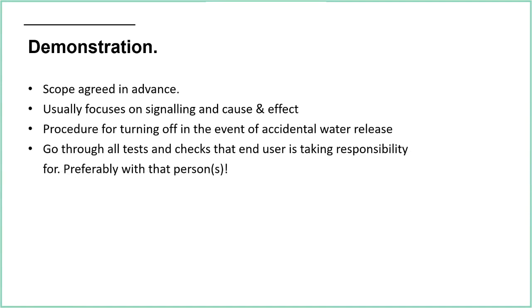Or it might be a case of 50%. So it might be a case of, just show me half of all the monitored valves, and I'll take it on faith that the other 50% work. Or it might be another percentage that is chosen. So say you're picking things at random to show that things are working without going through every single thing. Demonstration usually focuses on signalling and cause and effect, because that can be done from generally one location. You're setting things off, and do you get your signal, yes or no? It's quite a binary thing, isn't it? It either works or it doesn't work. So that's quite a good one to demonstrate to other people.